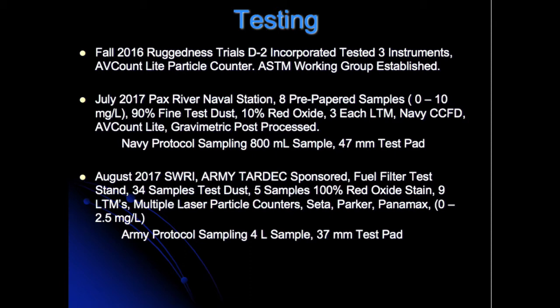In July of 2017, the Pax River Naval Station ran eight prepared samples from 0 to 10 milligrams per liter, with 90% fine test dust and 10% red oxide, using three light transmission method devices, the Navy CCFD device, the AVCount Lite, and gravimetric post-processed. Navy protocol sampling used an 800-milliliter sample with a 47-millimeter test pad.